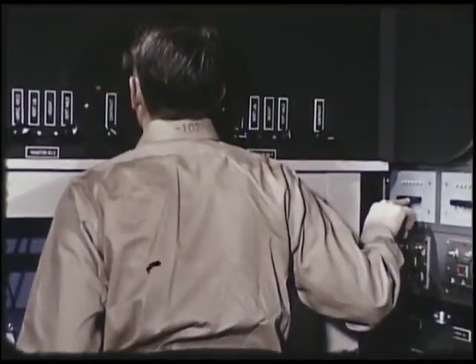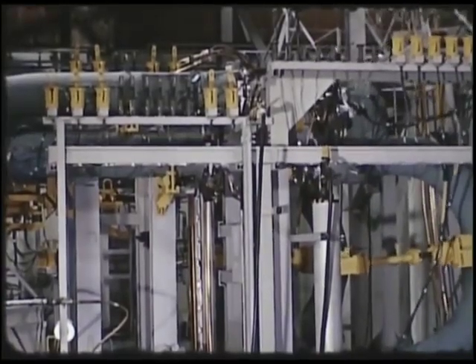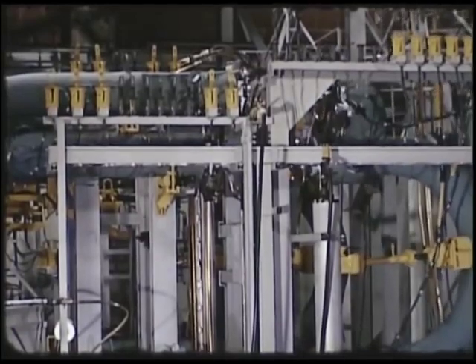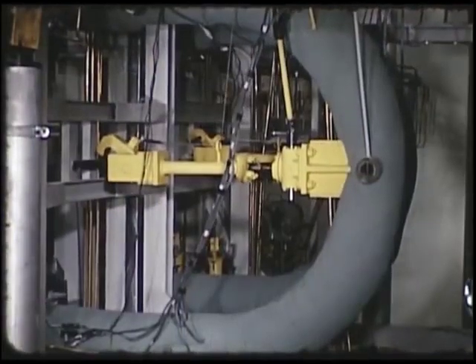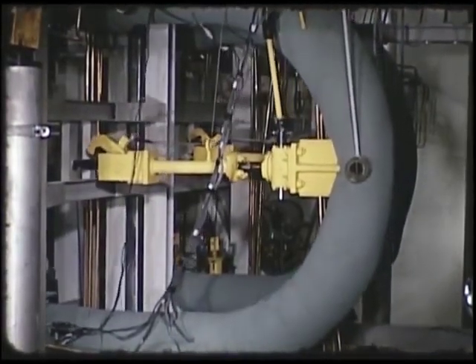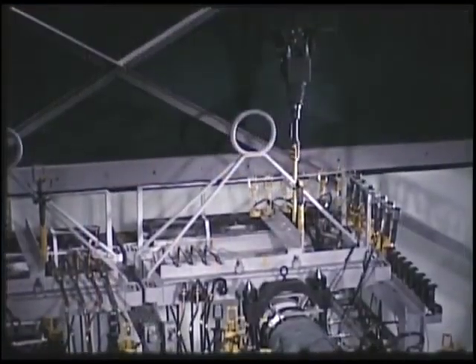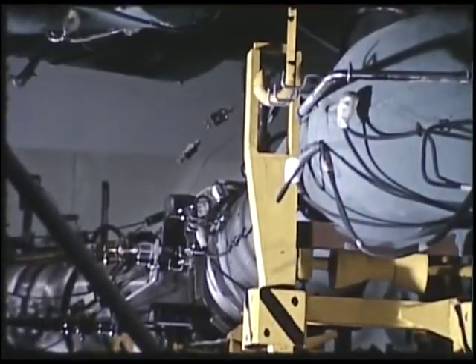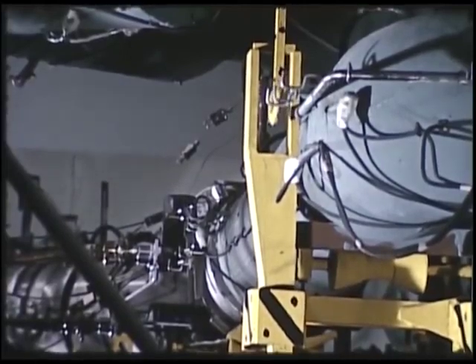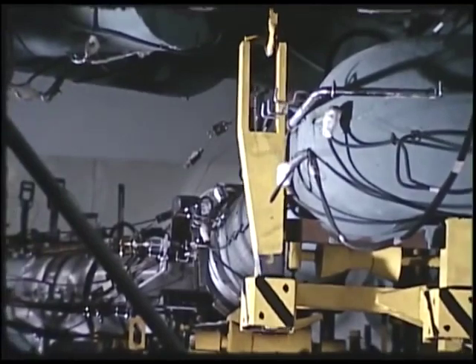A replacement heat exchanger is lowered onto the dolly track of the support stand. Then the unit is pulled into position for engaging the jack screw hook. After the hook is engaged, the control arm is actuated to mate the flanges. Finally, the wedges are removed. Total time required for removal and replacement of the heat exchanger is 24 hours.